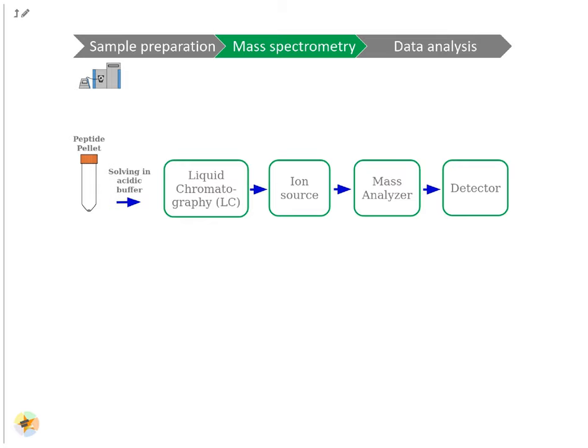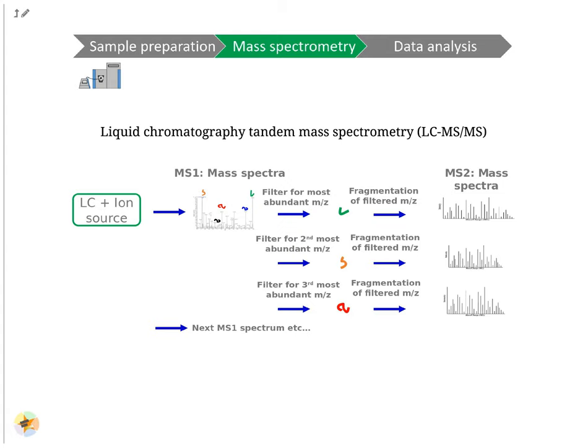Inside the mass spectrometer, the mass analyzer separates peptides based on their mass-to-charge ratio. The detector detects the peptide ions. Typically, explorative proteomics is performed via liquid chromatography tandem mass spectrometry (LC-MS/MS). While the sample elutes from the LC column, thousands of mass spectra are acquired. First, a mass spectrum of all peptides at each time point is measured. These mass spectra are called MS1 spectra.